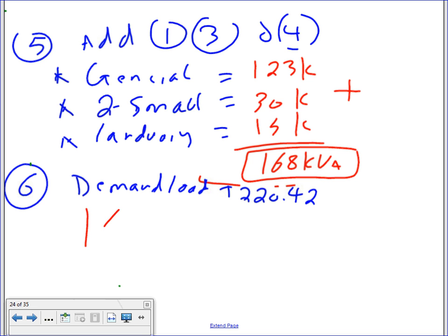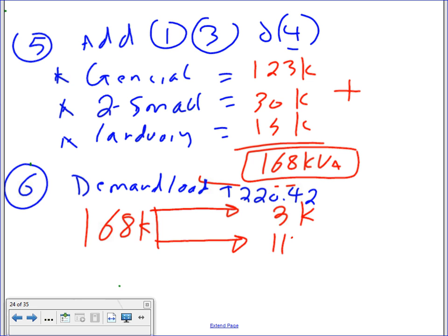You take the 168K and then you're going to split it into the following. The code says, guys, the first 3 shall not be touched. That's the first 3. Then, anything higher than 3 up to 117K shall be multiplied by 0.35. Then, all these are coming from where? From here, guys, right?